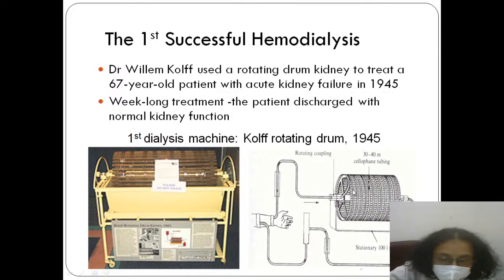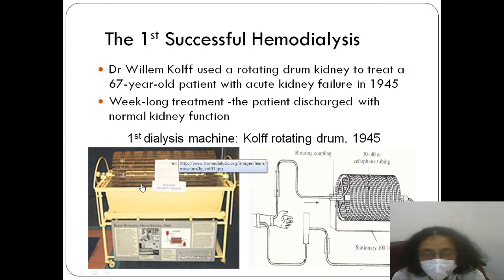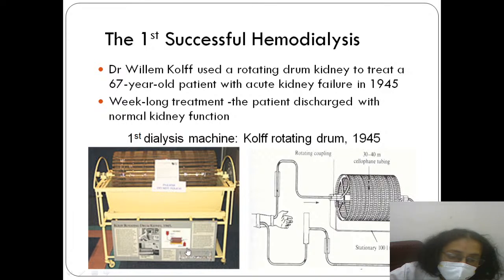So the blood is inside these tubes which are wrapped around a drum, and this drum is submerged inside the dialysate fluid, and this drum keeps rotating. So every part of the drum basically gets submerged, comes in contact with the dialysis fluid. So there's blood on one side of the cellophane membrane and there's the dialysis fluid on the other side of the membrane. So diffusion, convection, everything happens.